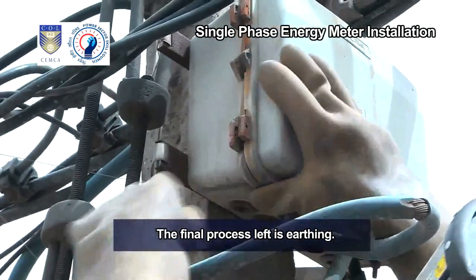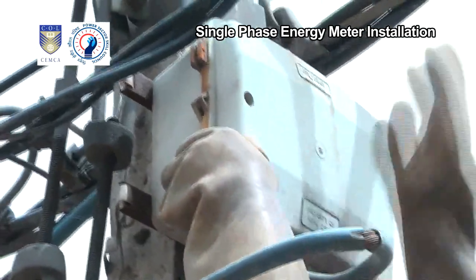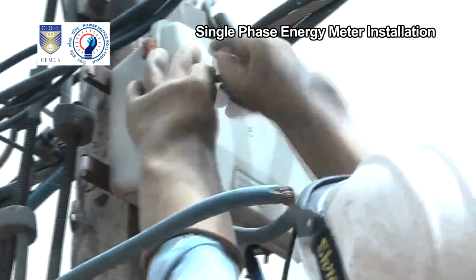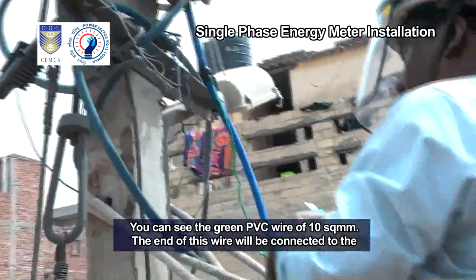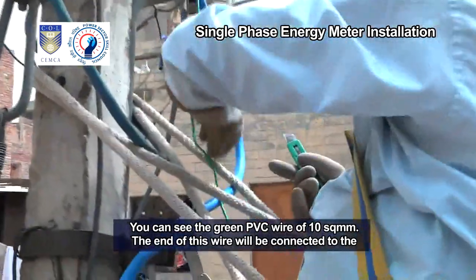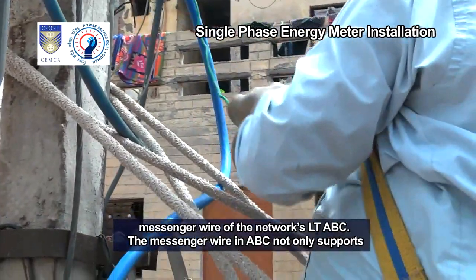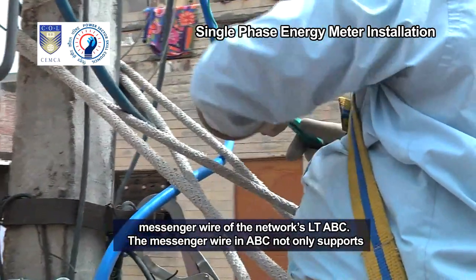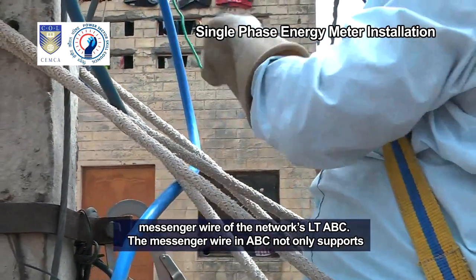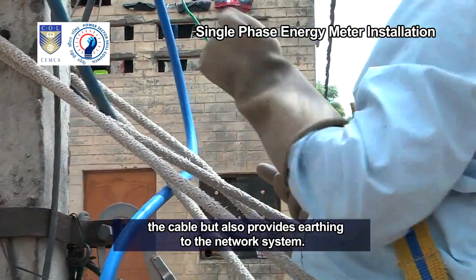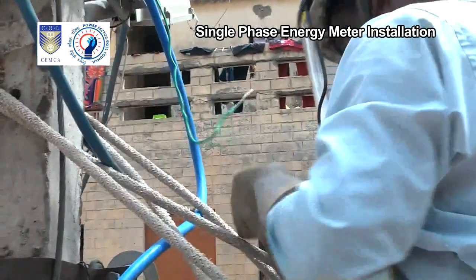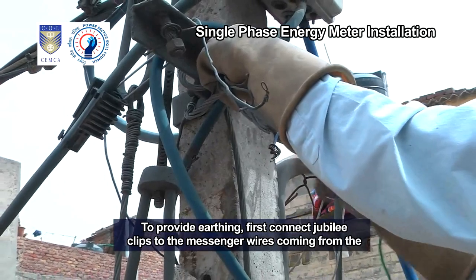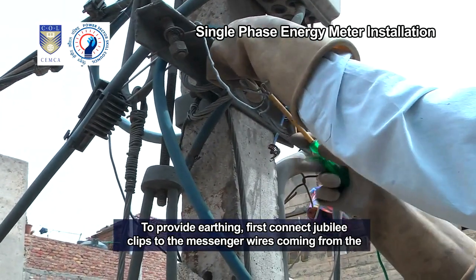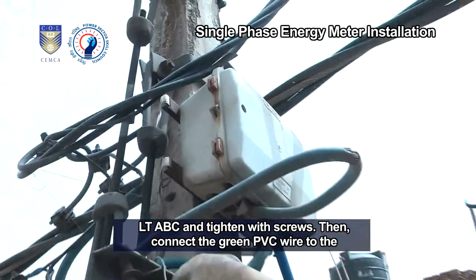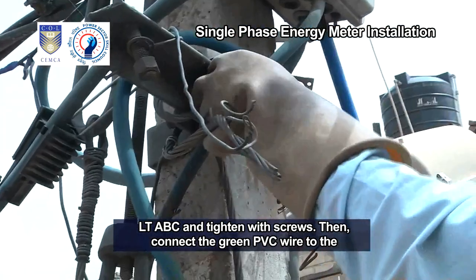The final process left is earthing. You can see the green PVC wire of 10 square millimeters. The end of this wire will be connected to the messenger wire of the network's LT-ABC. The messenger wire in ABC not only supports the cable but also provides earthing to the network system. To provide earthing, first connect Jubilee clips to the messenger wires coming from the LT-ABC and tighten with screws. Then connect the green PVC wire to the messenger wire through the Jubilee clips.